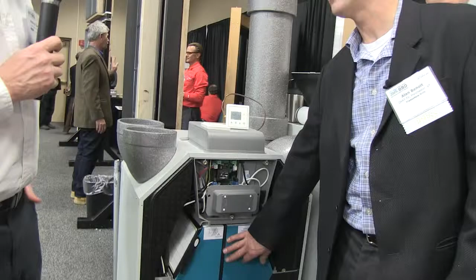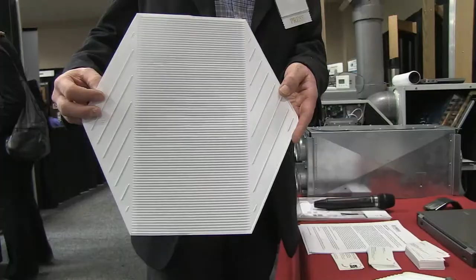What kind of material is the heat exchanger made of? These heat exchangers are made of polypropylene - the material is right here. We're able to get such high efficiencies because this is a counterflow heat exchanger. If you sliced a bunch of these down the middle, it would look like corrugated cardboard, with a lot of tiny cells where half the air flows in one direction and the other half flows in the opposite direction, passing by each other in parallel, allowing a large surface area for the most heat transfer possible. Thank you, Aubrey.